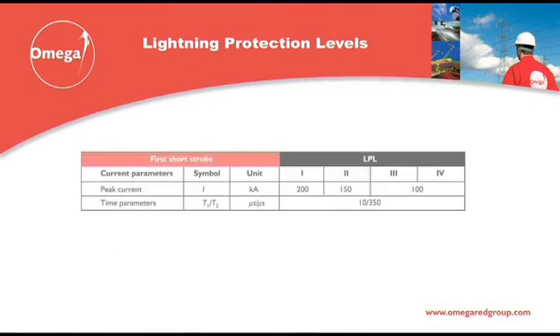There are now four different lightning protection levels. These are derived from the lightning first short stroke peak current, which is now attributed with a wave shape of 10/350 microseconds. Earlier British standards used a wave shape of 8/20 microseconds. The energy under the new wave shape is significantly greater than the old shape, and this has implications for the design of surge protection units. The maximum peak currents associated with the classes are 200,000 amps, 150,000 amps, and 100,000 amps for lightning protection levels 1, 2, and 3/4 respectively. These levels are determined by a risk assessment, which will be covered in the next section.